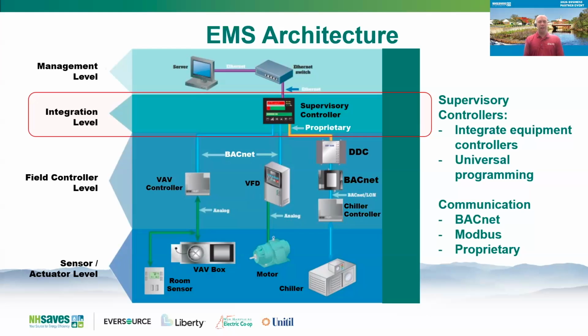You'll see that the graphic has the word proprietary in there, as well as BACnet. So BACnet is an open communication protocol that you can think of as like the language that we speak. We all speak English. Proprietary, you could think of as a foreign language that you may not be familiar with. That language is talked between the supervisory controller and the equipment controllers.